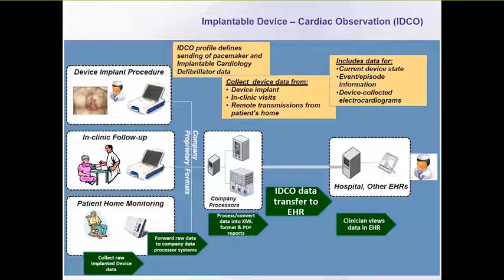Implantable Device Cardiac Observations, or IDCO, handles updates of implantable devices, such as a pacemaker or implanted defibrillator, through gateway devices that a patient will connect to at different times of the day, whether they be at home or in a clinic. These gateway devices, which normally connect back to a corporate server using raw data from the implanted device and then passed to those corporate servers via an XML or other proprietary format, then go to servers or gateways that they may connect to.